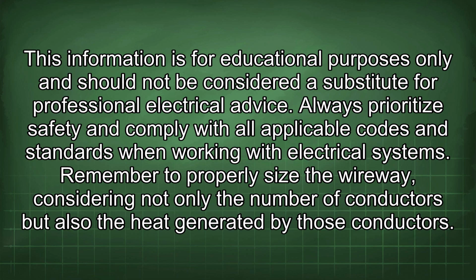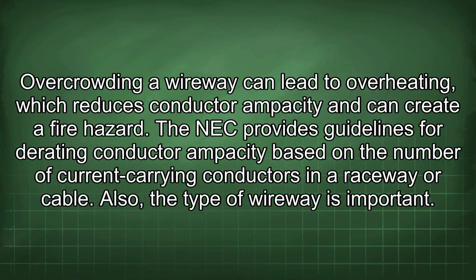Always prioritize safety and comply with all applicable codes and standards when working with electrical systems. Remember to properly size the wireway, considering not only the number of conductors but also the heat generated by those conductors. Overcrowding a wireway can lead to overheating, which reduces conductor ampacity and can create a fire hazard.